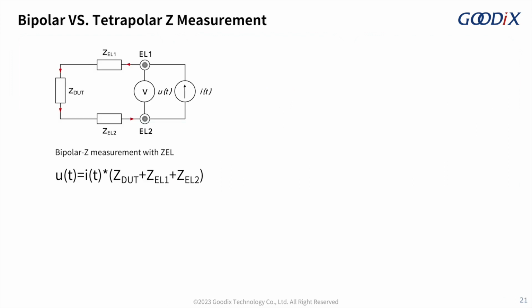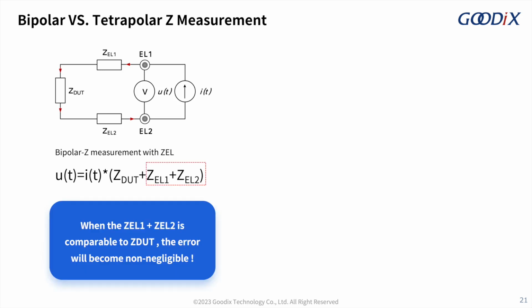The 2-terminal method features the simple connection. However, the measured impedance includes the contact impedance in addition to the DUT. When the contact impedance is comparable to the DUT, the error will be non-negligible. So this method is more suitable for measurement equipment with small contact impedance, or where the absolute value is not required.